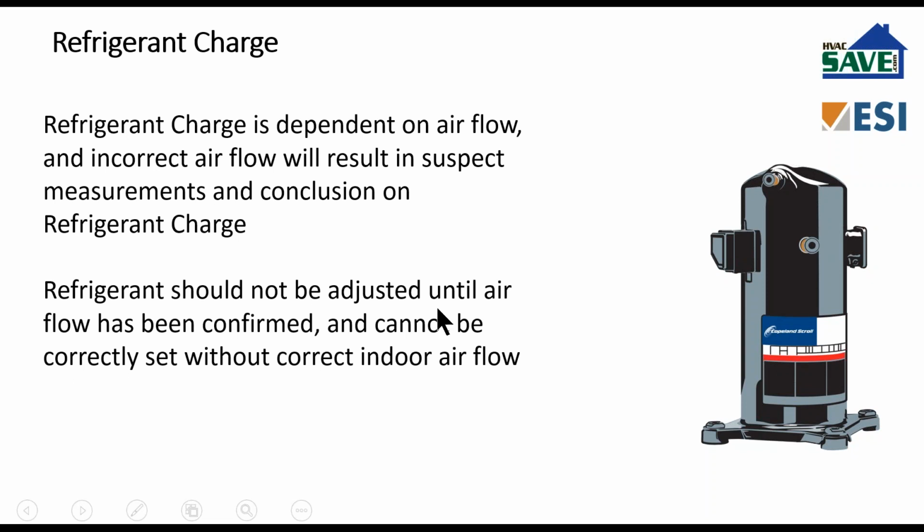Refrigerant should not be adjusted until airflow has been confirmed, and cannot be correctly set without correct indoor airflow. Again, reinforcing proper sequence, airflow first. Please don't mess around with your charge until you are totally confident in airflow, and also that airflow is correct to those OEM parameters.